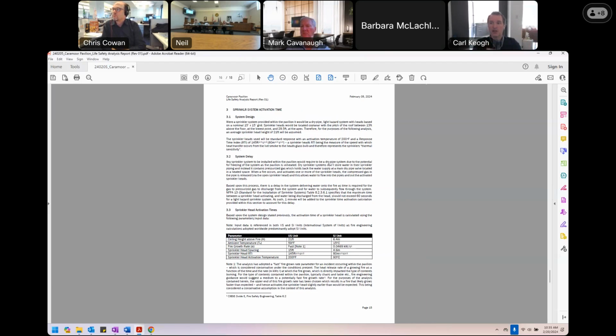So for any activation time, you have to add this 1 minute to take account of the fact that you need to fill the system. So again, similar to the smoke detection, there's a set of calculations that can be done, which I've done in a spreadsheet, which is in the report. Basically, for the type of sprinkler that you have, it has what's called an RTI, which is a response time index. That's how quickly it activates at a certain temperature, and you can calculate how fast the sprinkler system would activate.